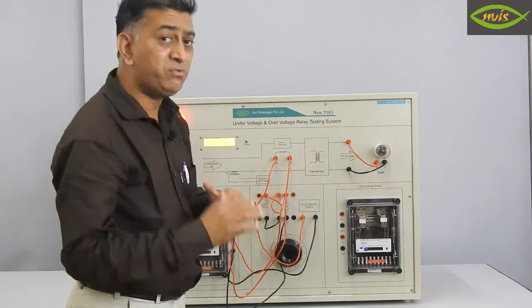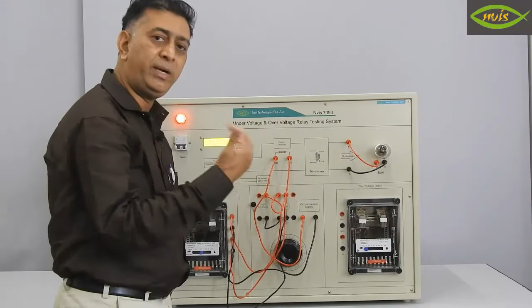Once it is operated, this white terminal, a metallic plate, will go above. Okay. The over voltage relay is in normal condition because we have not connected its connections right now. So we are performing only the under voltage relay experiment. To perform this experiment, the rating of this relay is 110 volt. So we have to keep in mind that we have to set this variac voltage to 110 volt. And in between, you will notice that the lamp will be switched on because the supply voltage will be more than the setting voltage. Since the setting voltage is around 65 volt, as I go beyond 65 volt, this lamp should be switched on. But later on, for performing the experiment, we will move it into the anti-clockwise position.